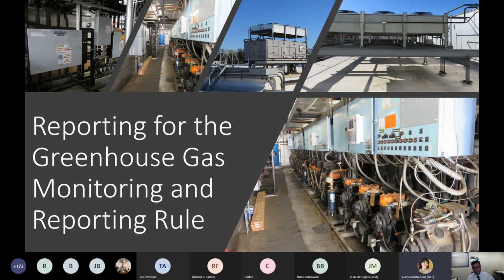Okay, moving on. Trisha Romano asks, what if your air conditioning system rooftop HVAC unit does not have more than 50 pounds of high GWP? That is excluded. Is this only for chillers? So any air conditioning system that is not a chiller is not required at all, regardless of how much refrigerant they have in them. If you're using a chiller for space cooling, then that chiller still would need to be registered.